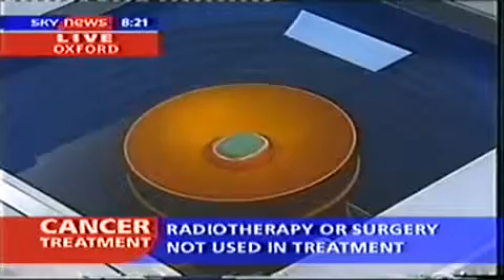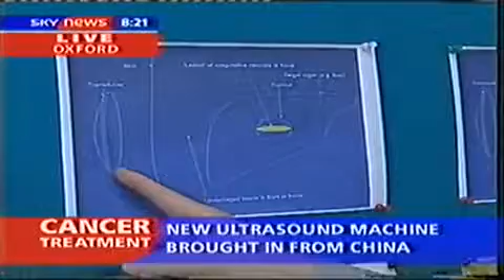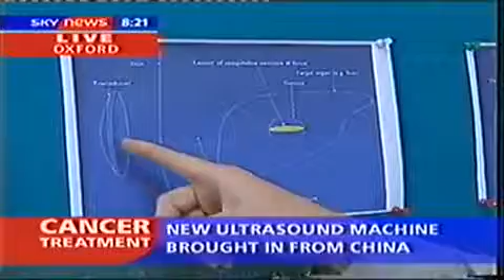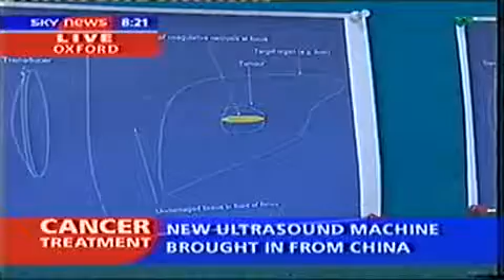The difference that this device has is, as you can see around the outside here, there is a much larger device, and this operates using higher intensity ultrasound, which carries a much higher energy level. That ultrasound is brought to a tight focus, and at that focus, that's where the tissue is damaged. One of the ways it's been explained to me is that most people will have taken a magnifying glass at some time and tried to burn a hole in a leaf. If you put the leaf in front of or behind the focus, you don't get any damage at all, whereas if you hold it right at the focus, you can see the leaf burning away. In a similar way, using sound waves, here is the orange bowl ultrasound transducer that you just saw, and you can focus these ultrasound beams and you get this cigar shape of tissue damage in the tumour that you're trying to treat.